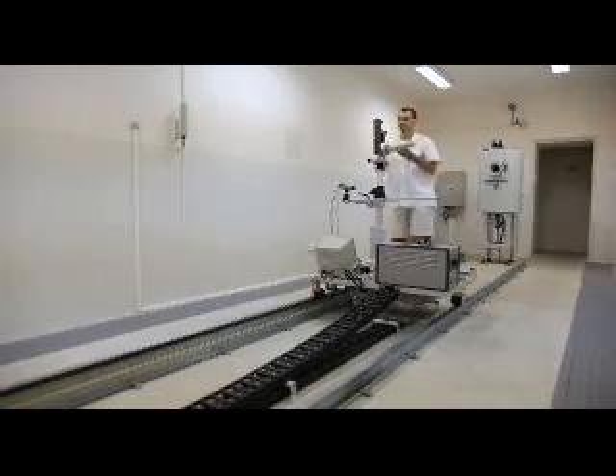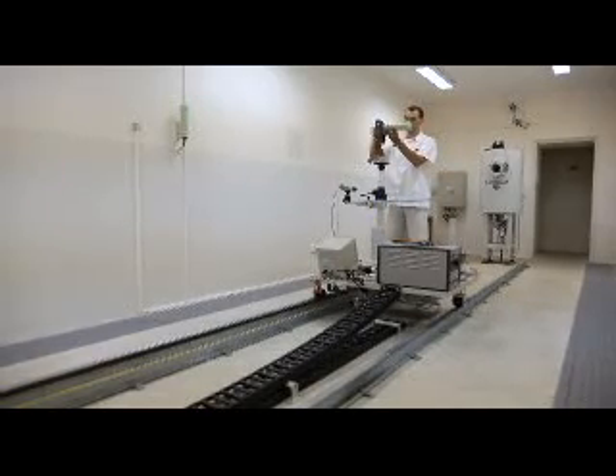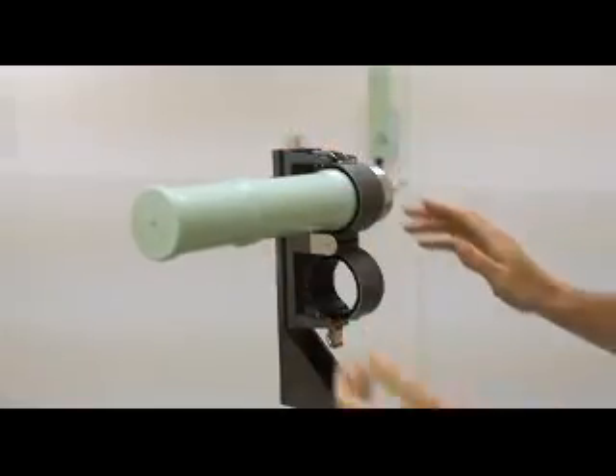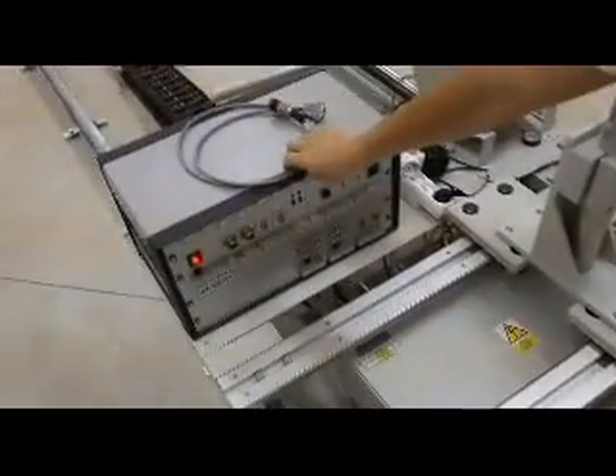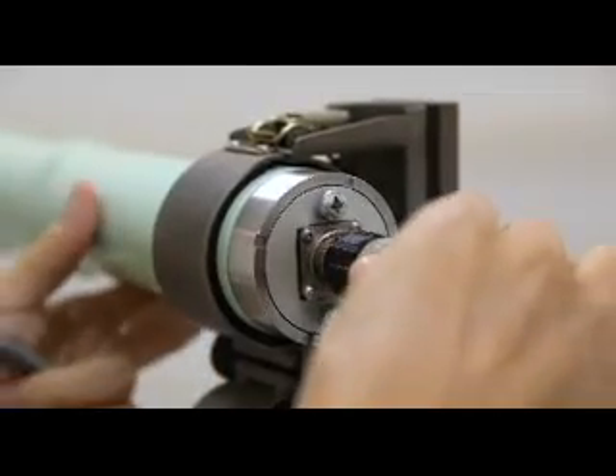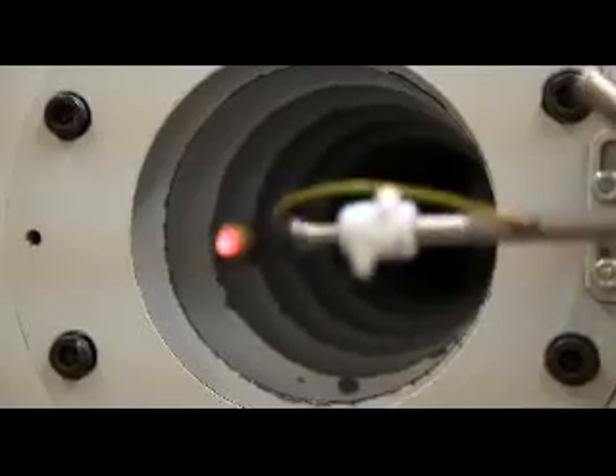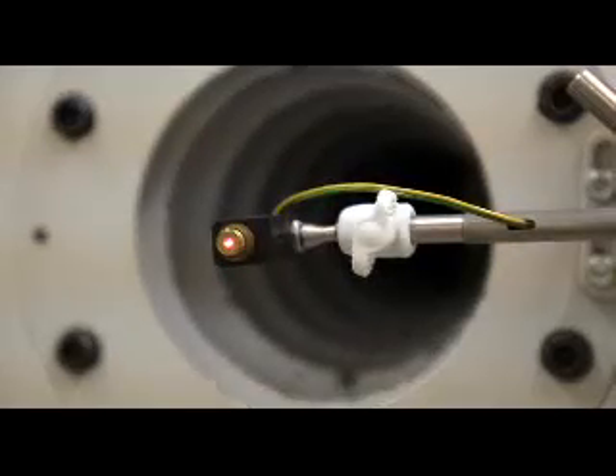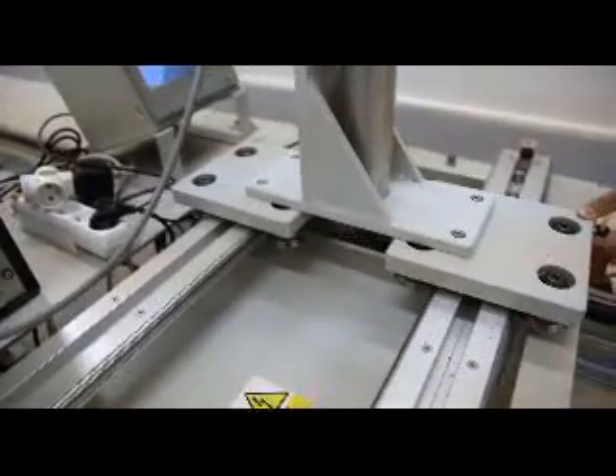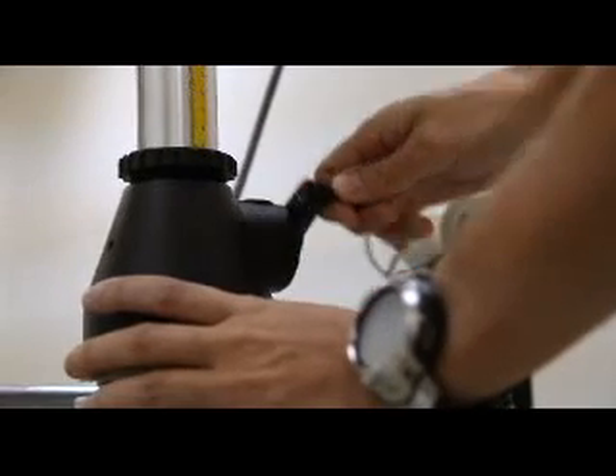After the recording procedure, the meter is mounted on the calibration bench using various jigs and fixtures. Depending on the type of meter being calibrated, we provide either versatile or tailor-made holders. After mounting, the meter is targeted using lasers and accurately positioned.